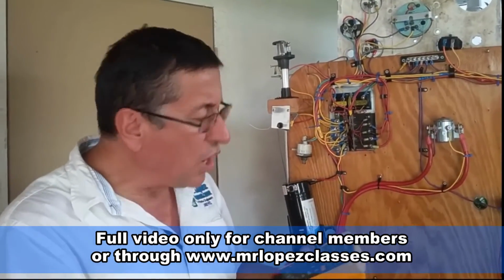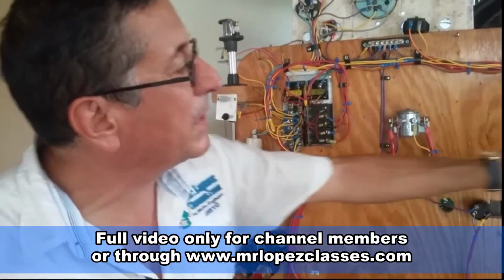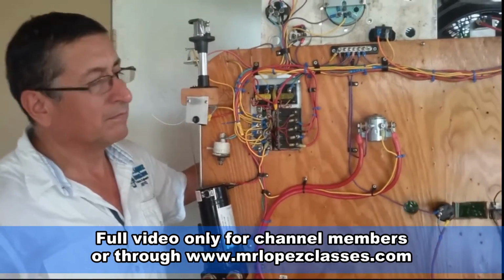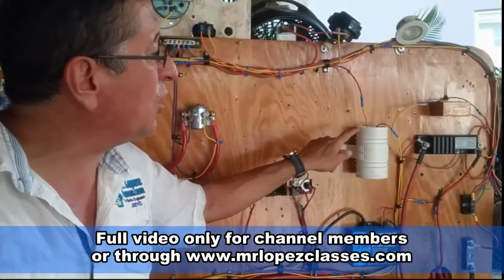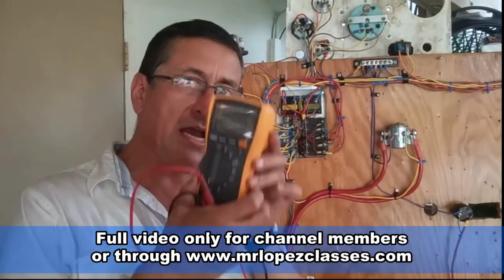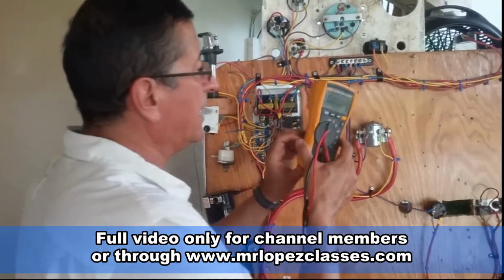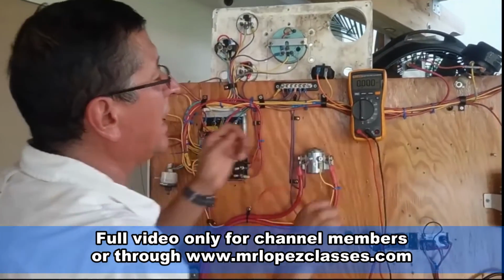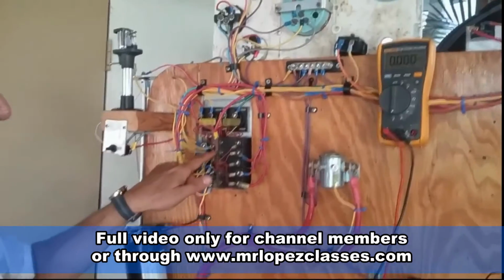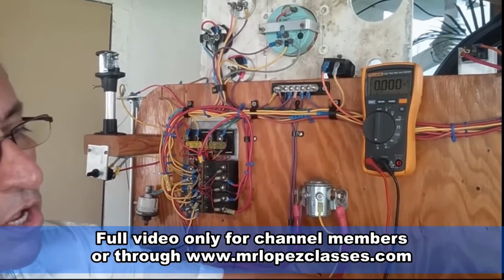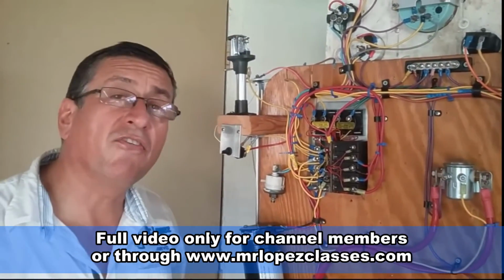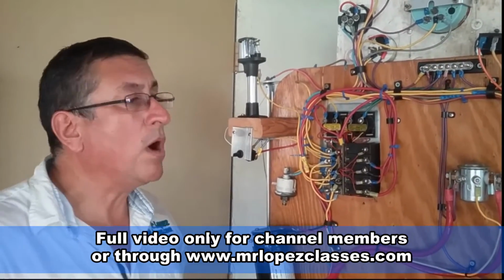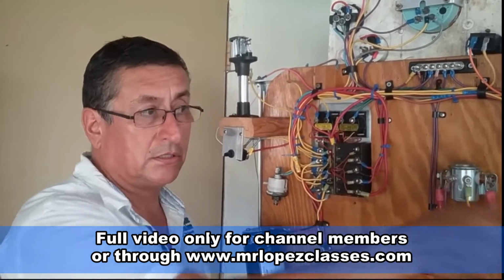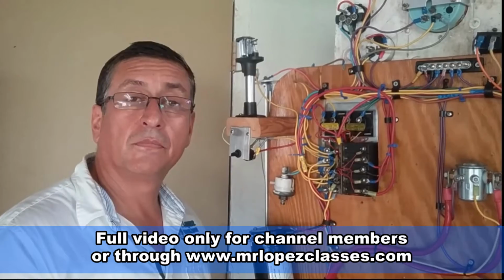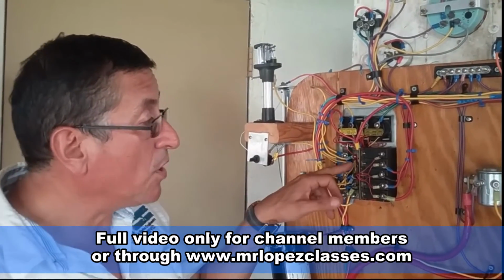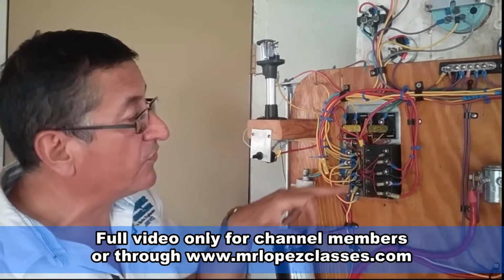Now, for example, I want to know the consumption of the blower, which is on breaker number 2, when the blower is running. I am going to use my ammeter. In this moment the breaker for the fan is off. The fan is not running. What happens when I close the contact on the breaker? The fan starts.